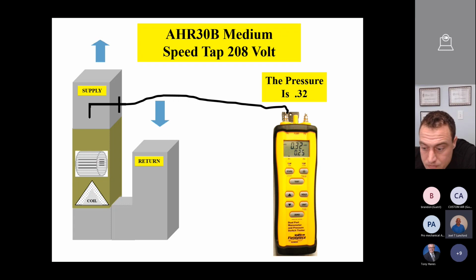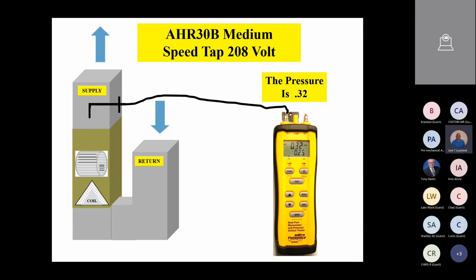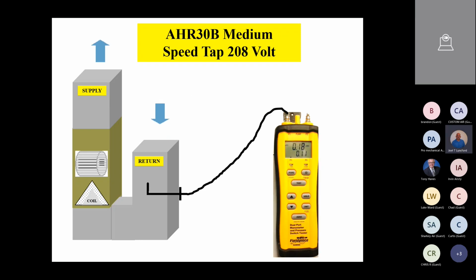And again, guys, I like taking my supply static first and then my return static. That's just how I do it in the field. And I take them separately, even though I have a 2-channel digital manometer, because I believe you get a more stable reading and a better reading if you take them separate and add them up. So that's how I like to do it. So 0.32 is our static pressure on the supply. Write that down. I then go to the return and I see I've got a return static pressure of a 0.18 inches of water column.